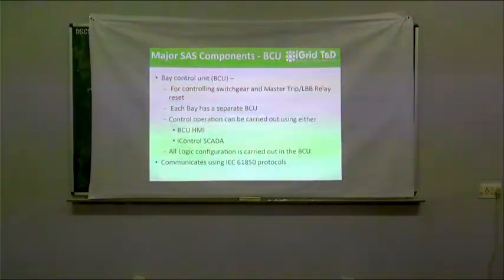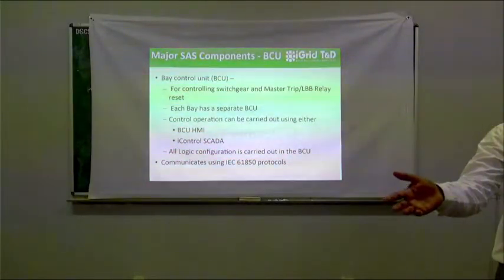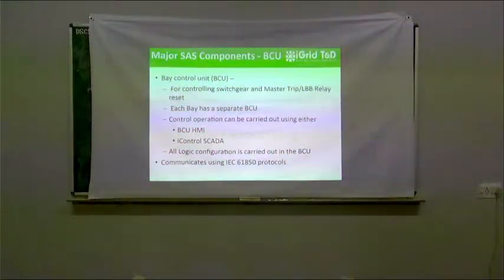In some cases this can also be a protection relay. It can work as an overcurrent or fault relay plus do the control operation. But the specification says the control operation and protection operation should be separate. That is the reason we give protection relays separately and bay control units separately. The objective is that at any point of time, even if the BCU is not working, it is fine, but the protection relay should always be working. That is the reason.